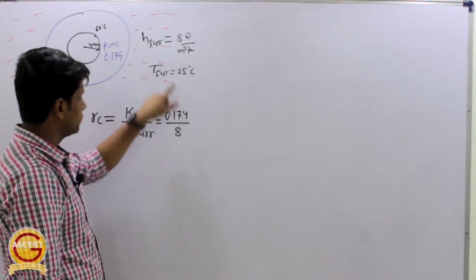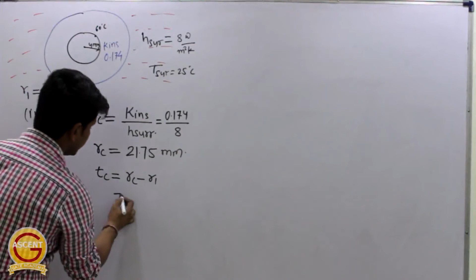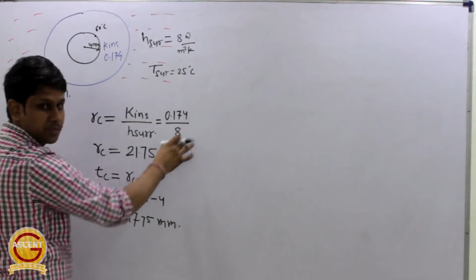Right? But he is asking for the critical thickness of insulation, or the thickness of insulation at which the heat loss is maximum. So what will be the value of this TC? I have told you how to calculate this thickness of insulation: it will be equal to RC minus R1. So if RC is 21.75 and R1 is given as 4, it will be 21.75 minus 4, so we will get 17.75. Correct? It is in mm. The value you get here will be in meters, so multiply by 1000 and you will get it in mm. So this is the first answer: the critical thickness of insulation, or the thickness at which the heat loss is maximum.